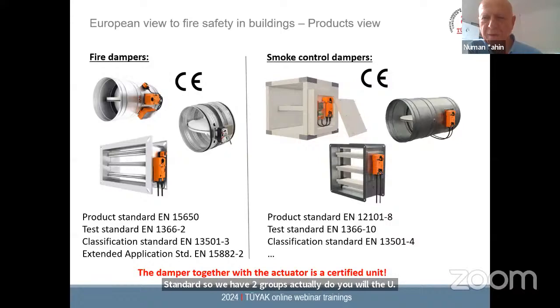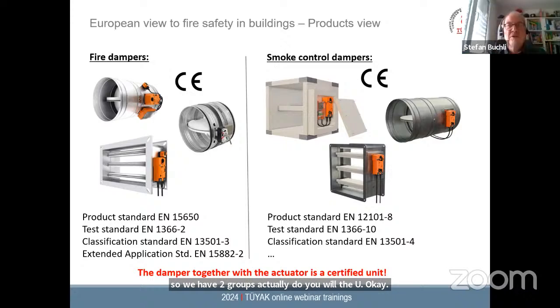What is the main difference? I mean, the torque or the opening or closing time? It's torque, it's running time, because different regulations are asking for different running times. And on the UL side, you have the so-called elevated temperature tests. So the actuator, after half an hour exposed to 250 degrees or 350 degrees Fahrenheit, must still be able to move the actuator or the damper to a certain position. And that's something we don't see on the fire damper side in Europe.